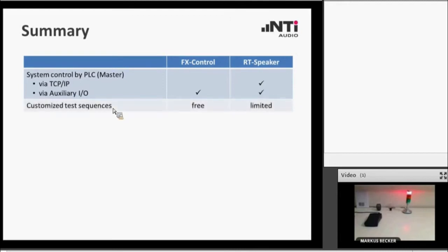Talking about the test sequence itself, FXControl offers you free definition of these test sequences with the features that are provided by the software, whereas RT-Speaker has a kind of predefined execution of these tests. You have a certain freedom to add more actions to that sequence, maybe to execute two different projects, to test two different devices with different test parameters in a row, but the basic execution is predefined, so your abilities to amend this sequence are restricted, whereas under FXControl you're absolutely free.